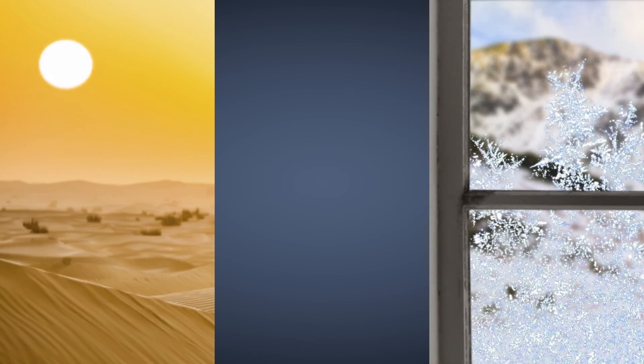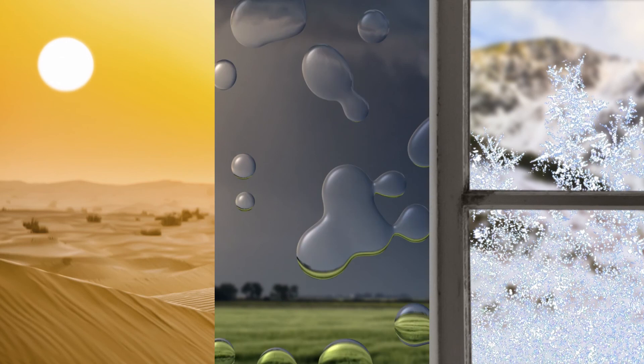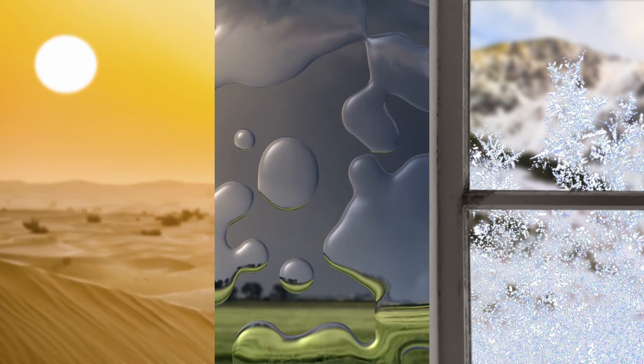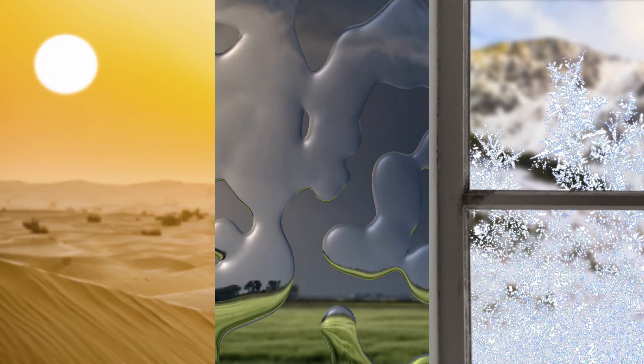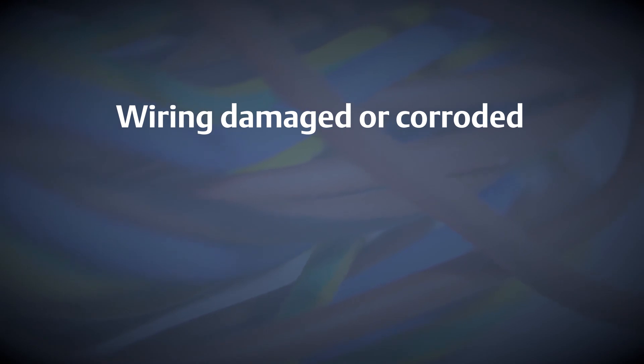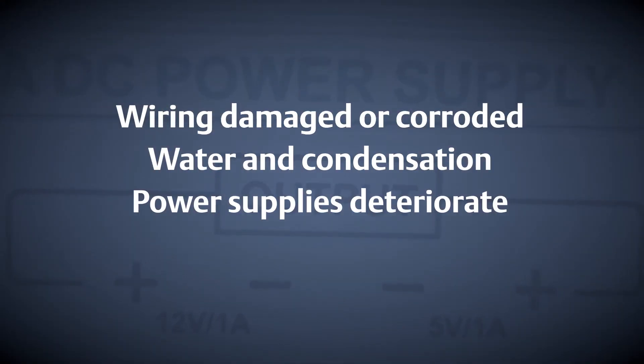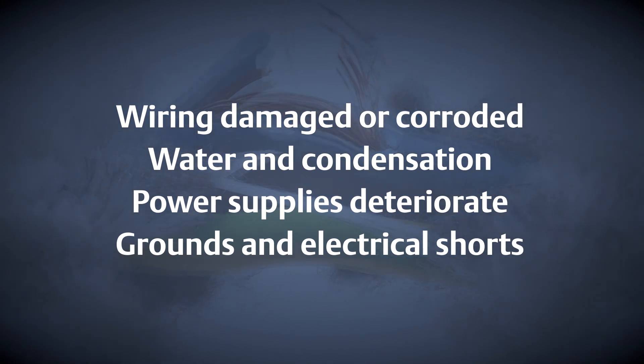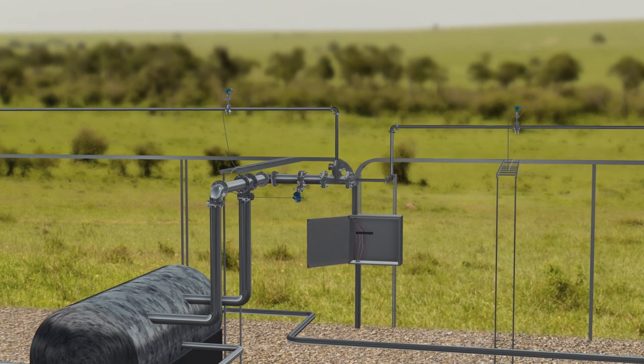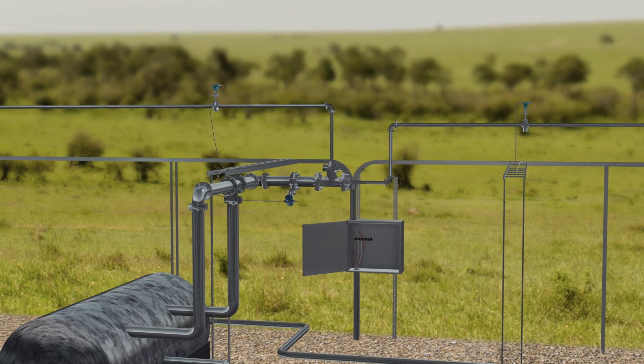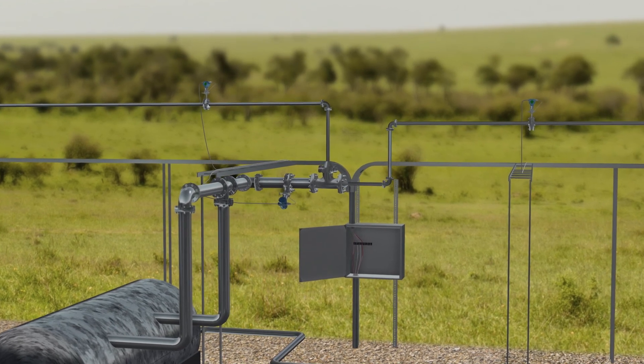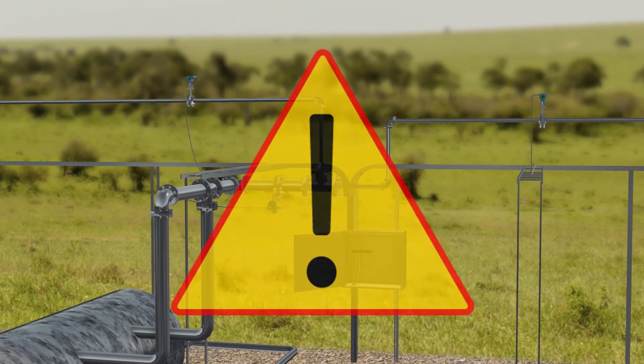Over the life of your plant, these critical components of your loop infrastructure are subjected to a variety of environmental and human stresses that can put the reliability of your 4 to 20 milliamp control loop at risk. Wires can become damaged or corroded. Water and condensation can find its way into housings and conduit. Power supplies can deteriorate and become unstable. Grounds and electrical shorts can inadvertently be introduced to the loop, causing the control room to receive inaccurate measurements and potentially lead to dangerous on-scale failures.